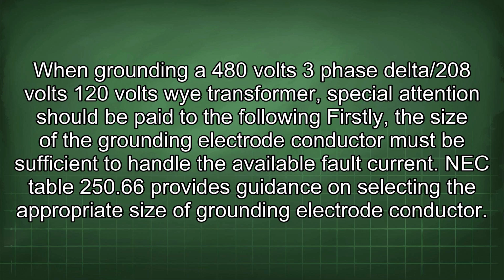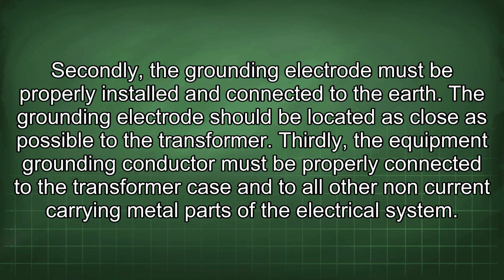When grounding a 480 volts 3-phase delta/208 volts 120 volts Y transformer, special attention should be paid to the following. Firstly, the size of the grounding electrode conductor must be sufficient to handle the available fault current. NEC Table 250.66 provides guidance on selecting the appropriate size of grounding electrode conductor. Secondly, the grounding electrode must be properly installed and connected to the earth. The grounding electrode should be located as close as possible to the transformer.